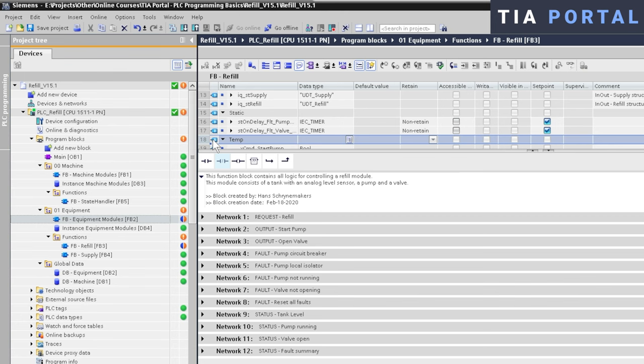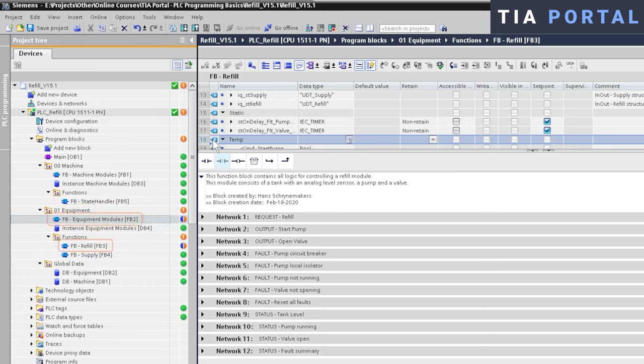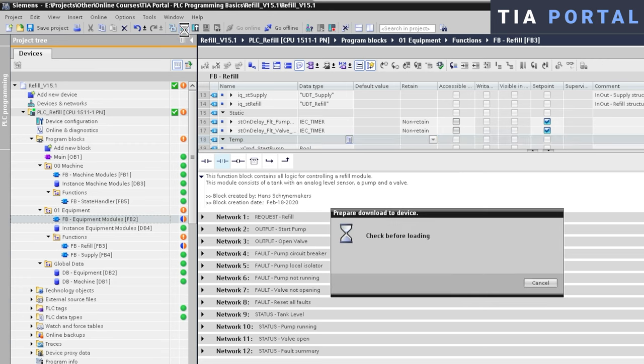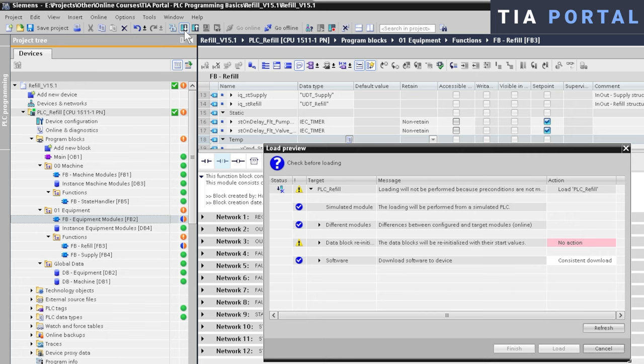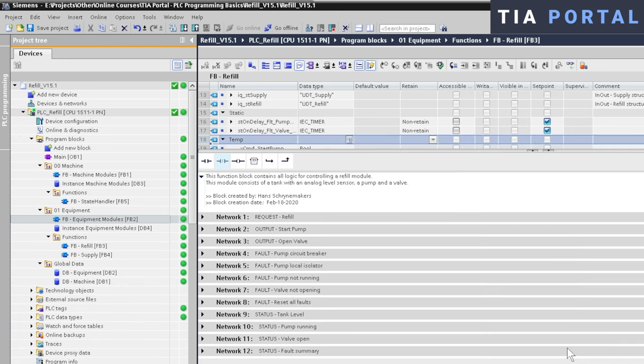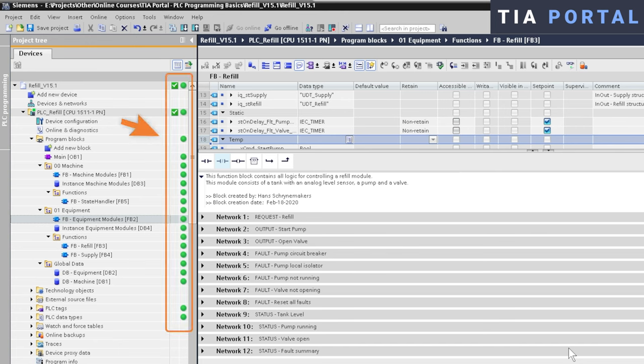Keep an eye on the green indicators while I delete this variable. We can see that two group indicators changed from green to orange with an exclamation mark, and two blocks changed from green to a half orange, half blue color. These color changes indicate that these groups and blocks are not consistent anymore with the online project and a download is required to update these blocks in the controller. So let's download the application. And as we've covered before, TIA Portal will automatically compile all blocks and only download the blocks related to the changes.